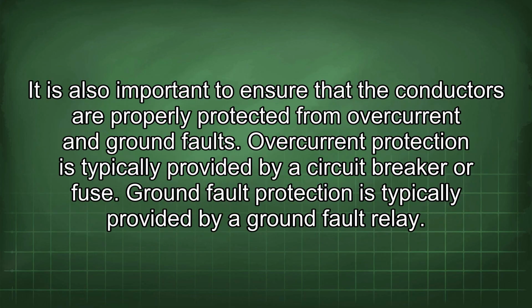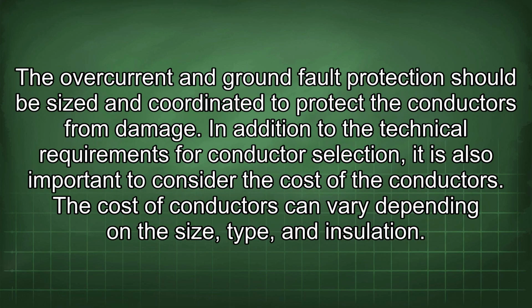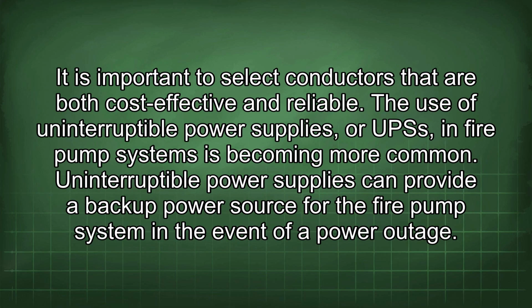It is also important to ensure that the conductors are properly protected from overcurrent and ground faults. Overcurrent protection is typically provided by a circuit breaker or fuse. Ground fault protection is typically provided by a ground fault relay. The overcurrent and ground fault protection should be sized and coordinated to protect the conductors from damage. In addition to the technical requirements for conductor selection, it is also important to consider the cost of the conductors. The cost of conductors can vary depending on the size, type, and insulation. It is important to select conductors that are both cost-effective and reliable.